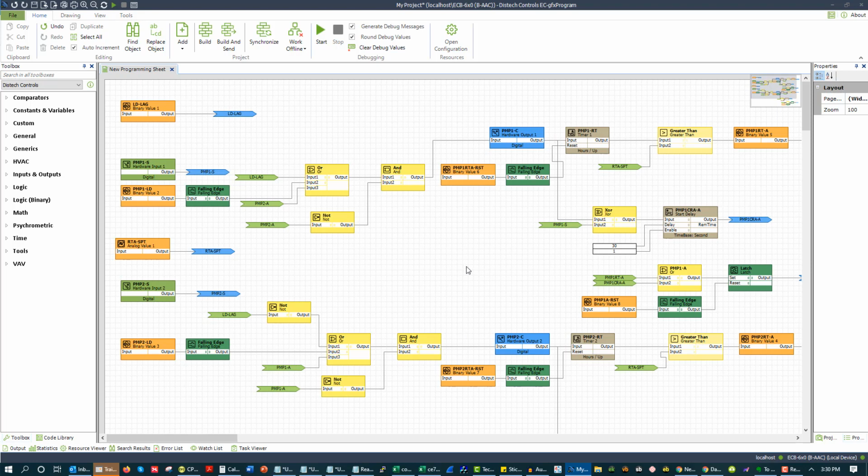And there's pros and cons to that. There's the pro in that you don't actually have to take the controller offline to do code changes, so that's nice. The downside of that is that the controller's not offline when you're making code changes, meaning you're making code changes to live code in a controller, which can really hose stuff up. So you need to be cognizant of when you're actually going and making those changes. Just be aware of how all that works.